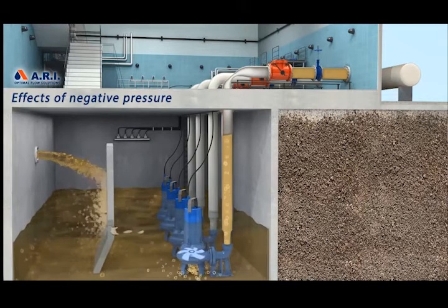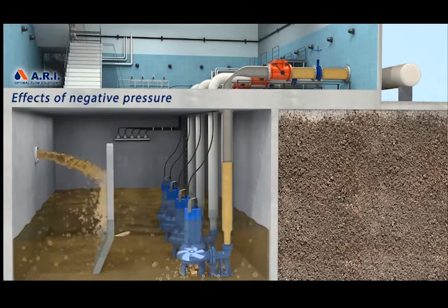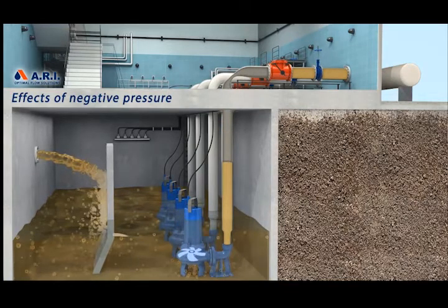An additional hazard is when we drain down the pipeline. If we don't allow air to be intaked, that causes the pipe to have negative pressure that could lead to collapse of the pipe, or could lead to negative stresses on the main water column.